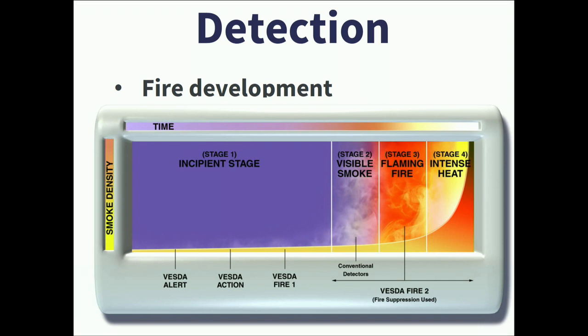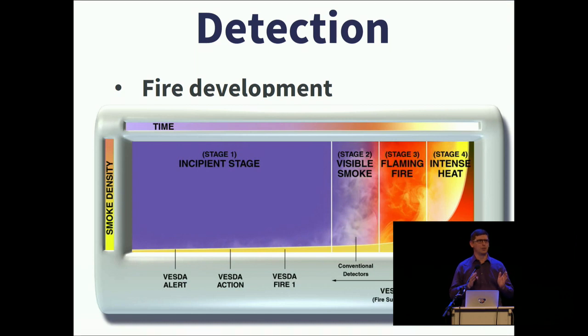And as that progresses through the stages, going to VESDA action, and then VESDA fire, it can be quite a bit of time before a smoke detector head, so one of those ionizing or optical heads, will actually detect a true plume of smoke. So there is a big stage there of what do you do when you get a VESDA alarm. Most data center operators send people to investigate it, and that's the sensible thing to do because you know it's in the very, very early stages.